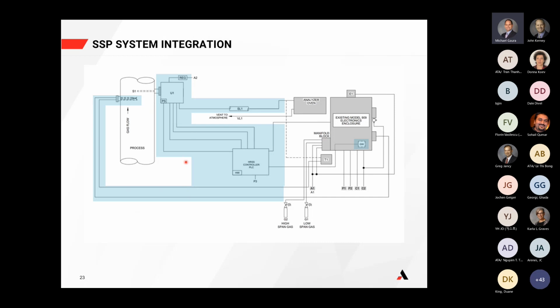And building upon that, I think we might have gone through this too quick earlier. As we're looking at this picture right here, that controller, the severe service probe controller, could be sitting right in the same enclosure as the analyzer. It doesn't need to be 3 inches away from the blowback probe on top of a stack somewhere. So there's a lot of flexibility in where that would get located. Okay, a couple other questions around controller operation features. One is, does the controller allow for the analog output hold in the analyzer?